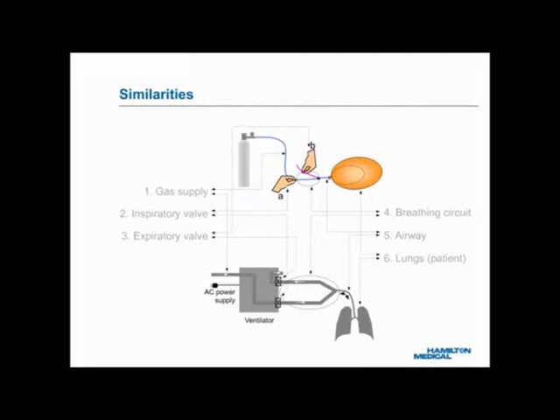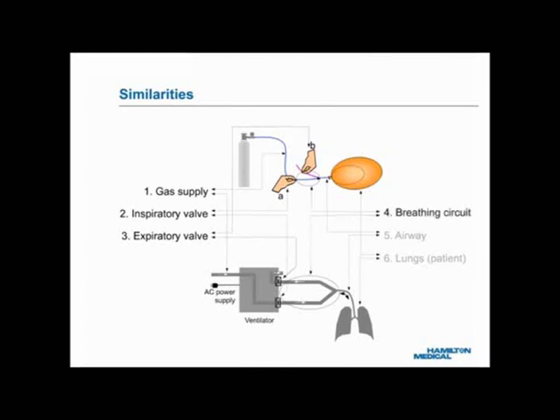The balloon model is highly comparable to a real ventilator system. One: the cylinder in the model corresponds to the high-pressure gas supply; a ventilator system needs high-pressure oxygen and high-pressure air. Two: Hand A corresponds to the inspiratory valve. Three: Hand B corresponds to the expiratory valve. Four: the blue and pink tubes between the Y piece and the two hands correspond to a breathing circuit. Five: the blue tube piece between the Y piece and the balloon corresponds to the airway. Six: the balloon corresponds to the lungs of a ventilated patient.